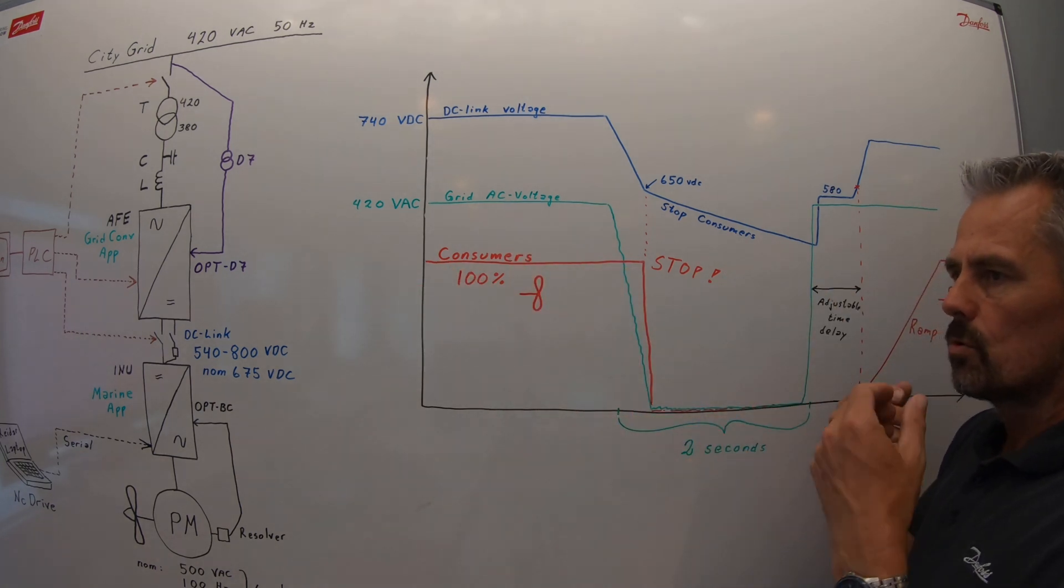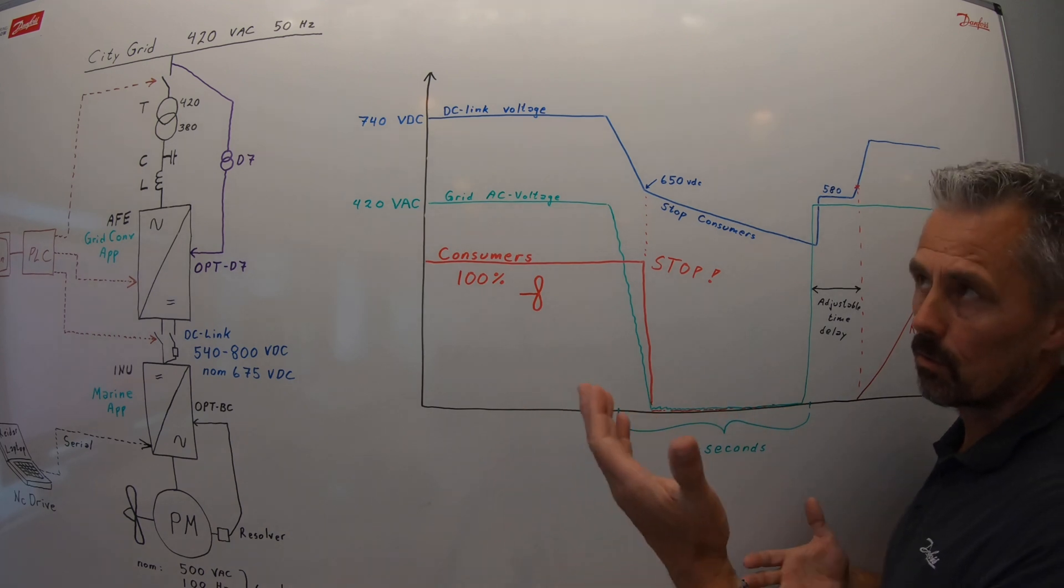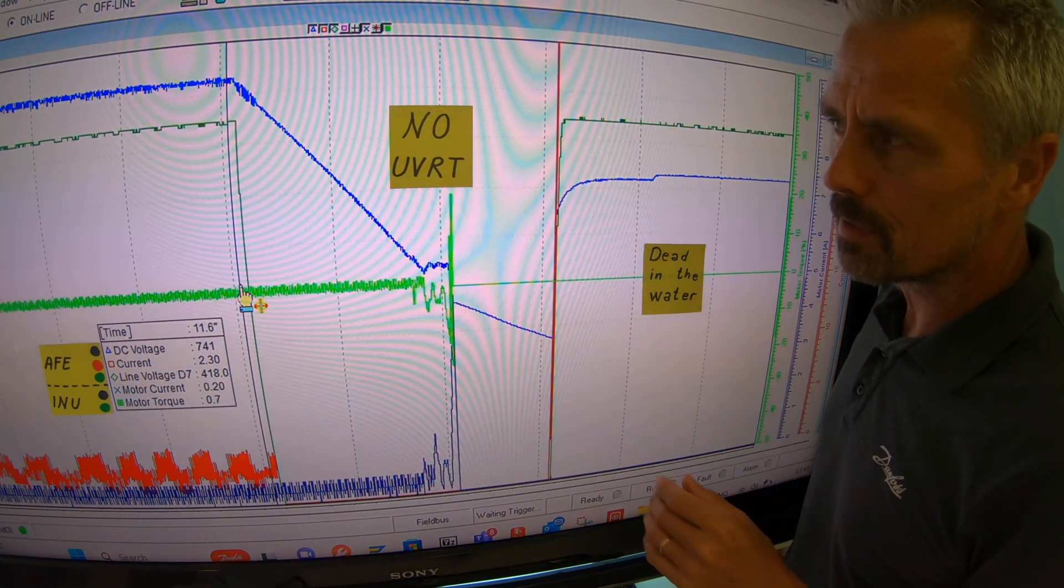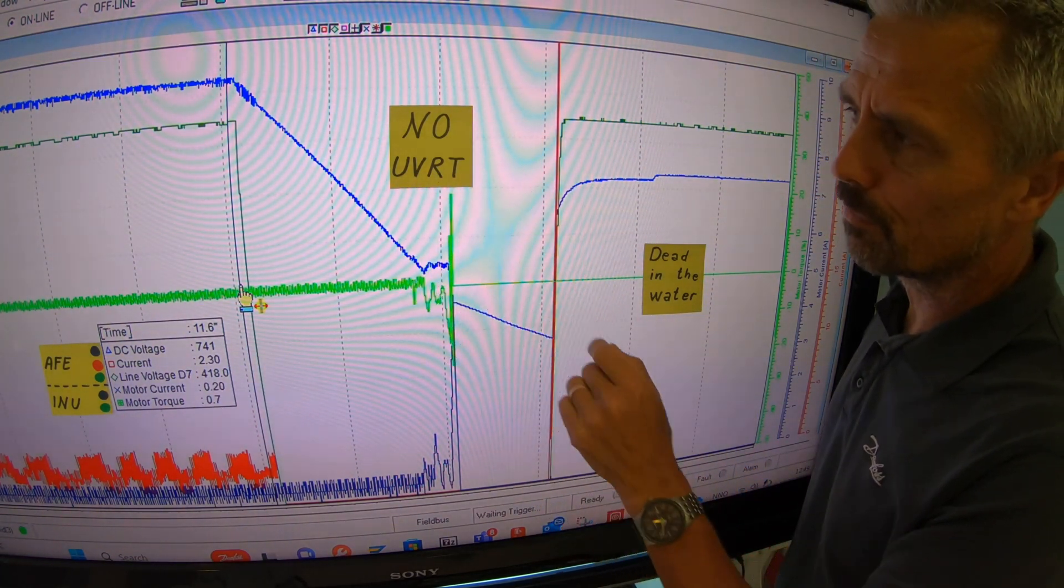So you put some seconds delay between them, so they start up in a sequence. And this way, you soften the load on the diesel gensets or the grid converters. For reference, let's see what happens without the undervoltage ride-through activated.